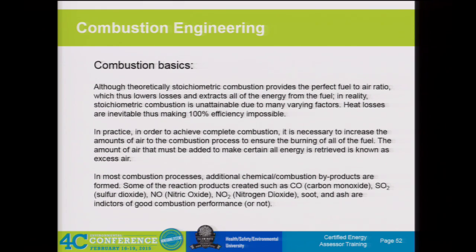We're going to generate SO2 and NOx compounds as part of the process. We have fuel-bound sulfur and nitrogen in the fuel, and that's going to drive the generation of other compounds during the combustion process. Soot and ash are also indicators of how the combustion performance is working. If we're getting char and carryover—unburned particles—that is an indicator that we're not getting the right temperature or turbulence in the combustion zone to complete the reaction, or we don't have enough air in the system.